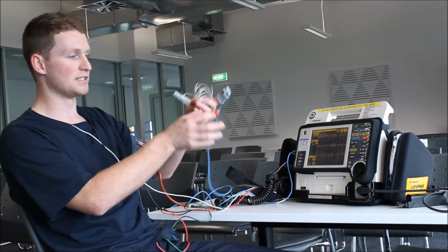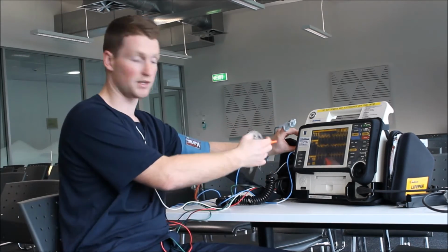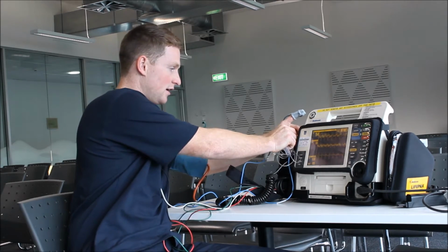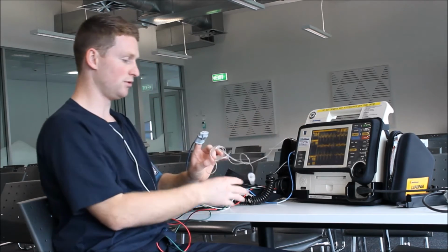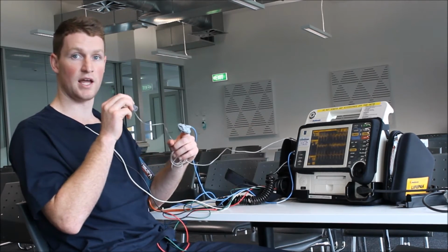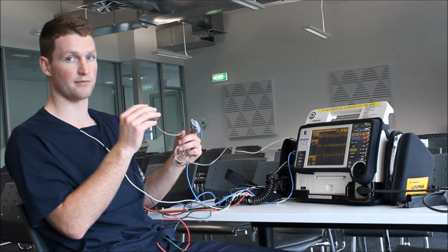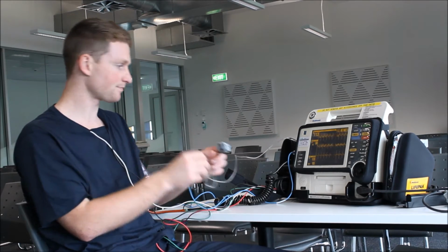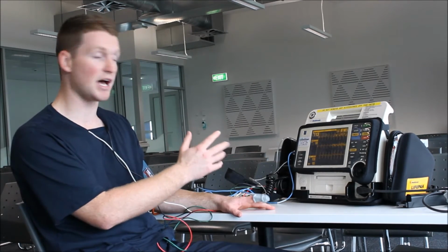What we're going to do next is identify the CO2. There's this one here on the side, and this orange one you screw into the top on the left of the LifePak, just above the SpO2, and then you attach this into your breathing mask, and that will detect how much CO2 has been blowing off from each breath, which is quite handy as well.